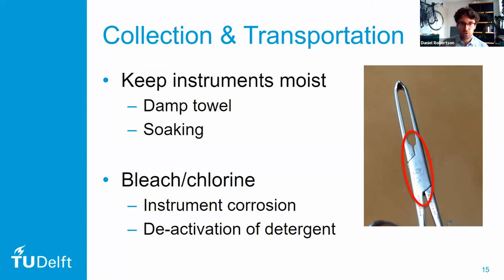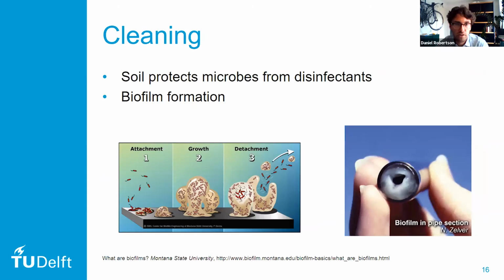Now, the other disadvantage of using chlorine is that it deactivates the detergents and disinfectants, so the rest of the steps become less effective. Now, after transport, we have to clean the instruments. Proper cleaning is by far the most important step of the reprocessing cycle. Now, why is it so important? Well, the goal of cleaning is to reduce the bioburden and microbes on the device so that they can eventually be safely disinfected or sterilized.